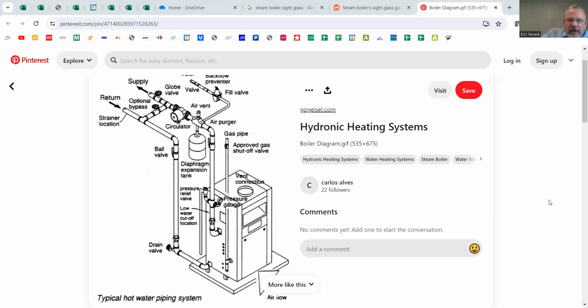Okay. So Randy mentioned a pressure relief valve, or Wayne or one of you guys did. Now that's going to be present on any boiler. It's a safety device, and it's going to be there on a water heater. It's going to be there on a boiler as well. And if you see below the diaphragm expansion tank is labeled pressure relief valve. So it's a small valve. It looks very much like a pressure relief valve on a water heater, except there's a key difference there. On a water heater, it's a T&P valve, meaning temperature and pressure relief valve. So the one on a water heater will open if it gets too hot, and it will also open if it gets too high in pressure.